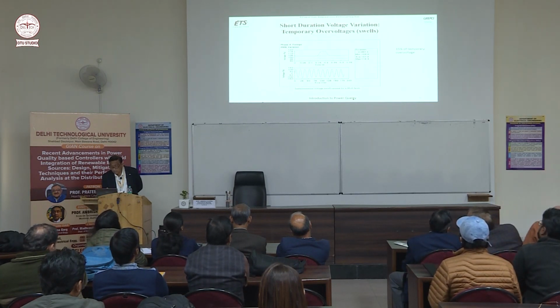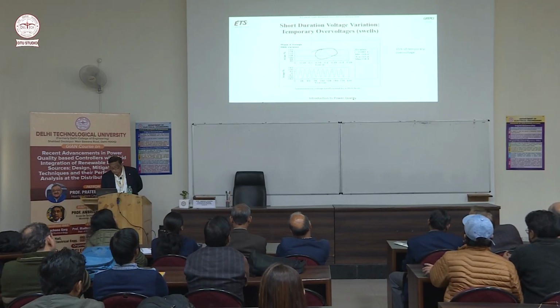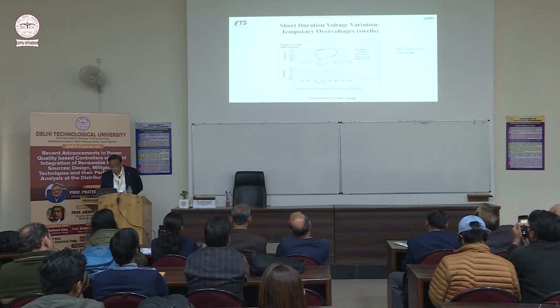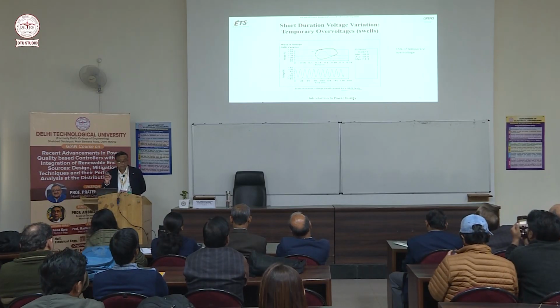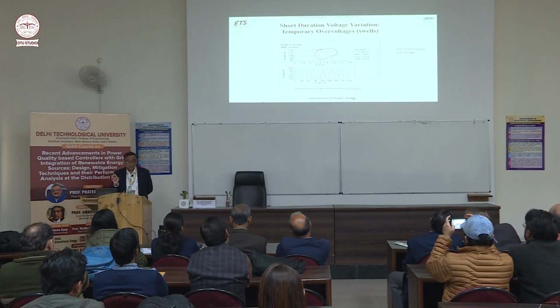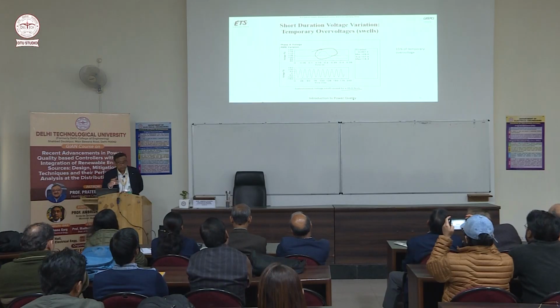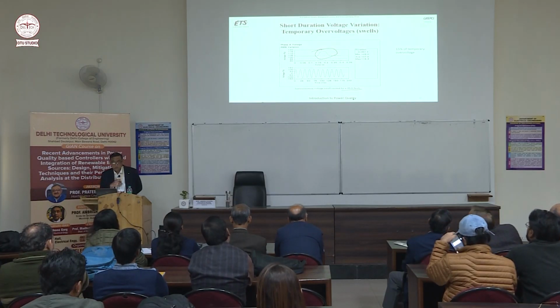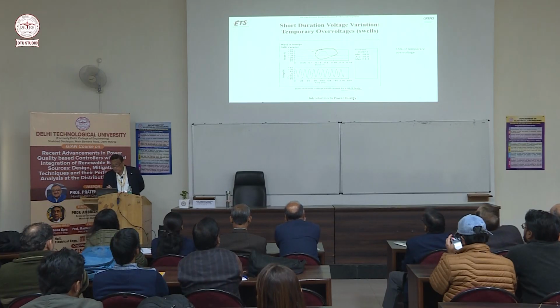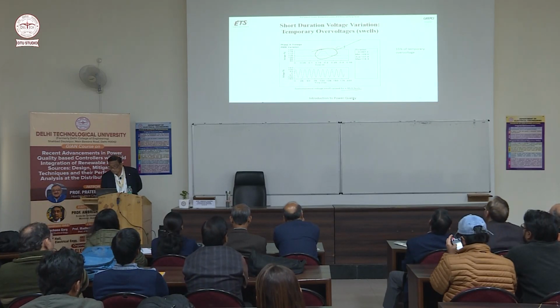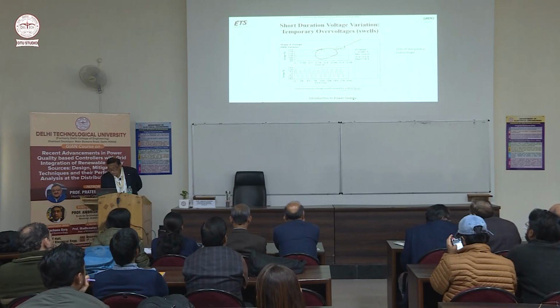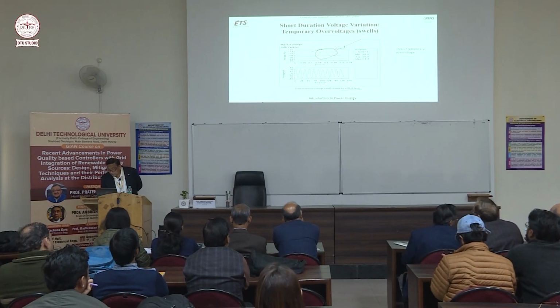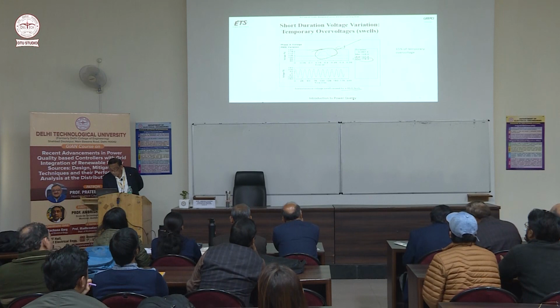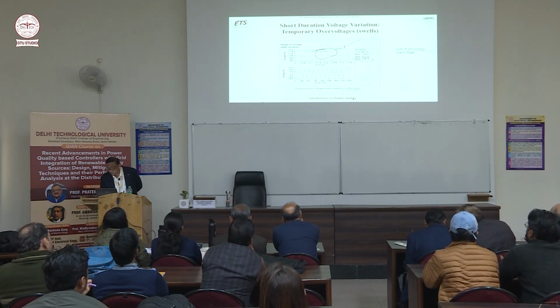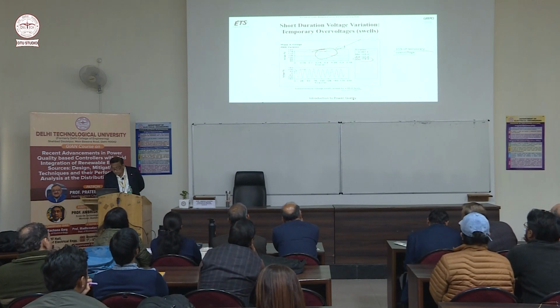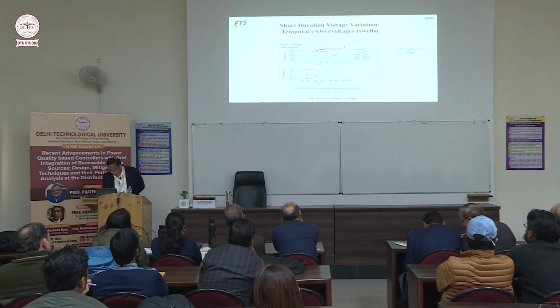So this is just an example of the swell. Okay, it is caused by single line to ground fault. Suppose there are two parallel lines, and if one parallel line is tripped, then the voltage may increase on the first line because there will be less current, less drop. So because of that, voltage swell is there. So in this case, you see, maximum it has gone to around 15% temporary over voltage. Although this is not very clear, but it is here.